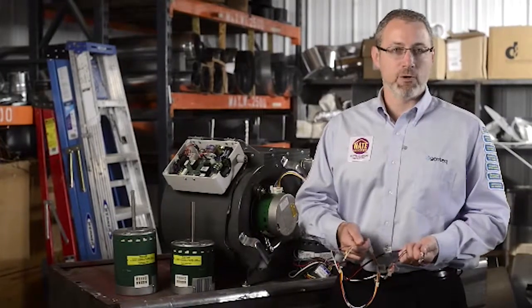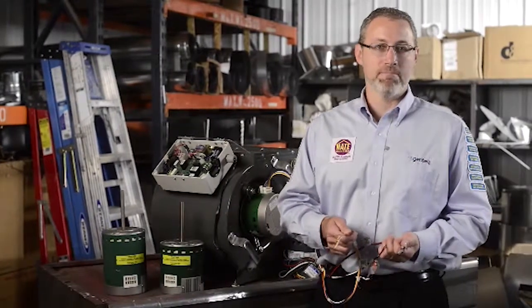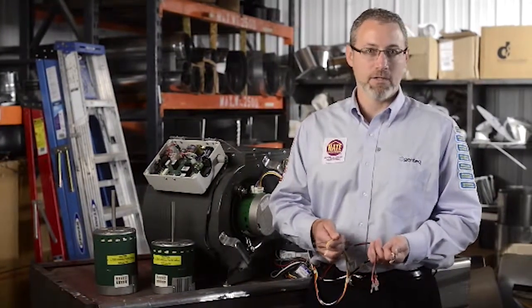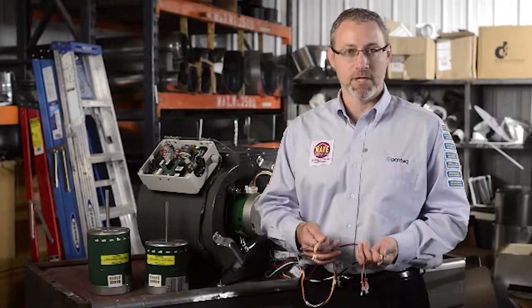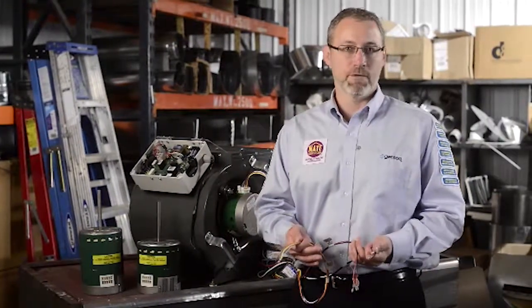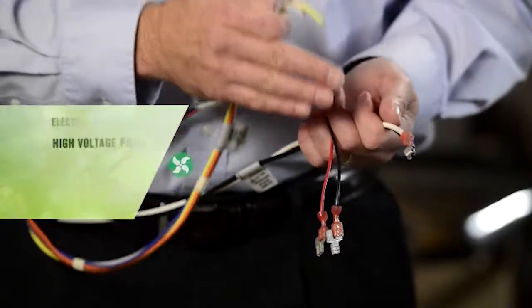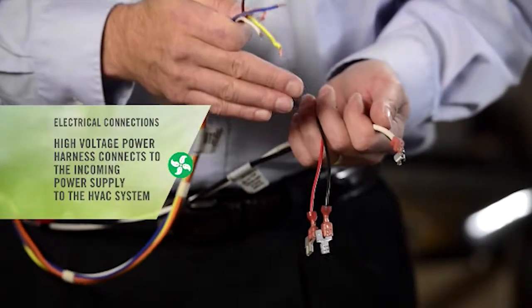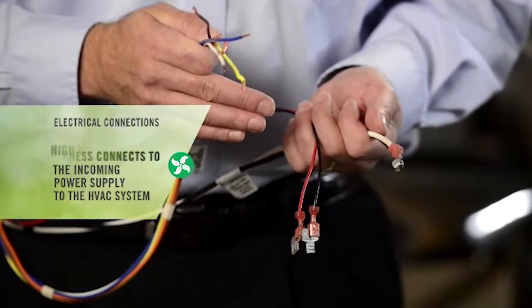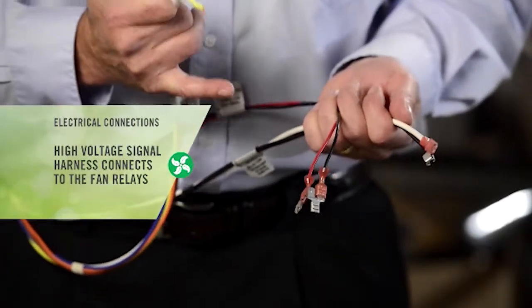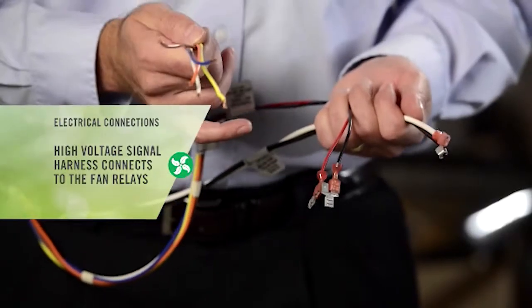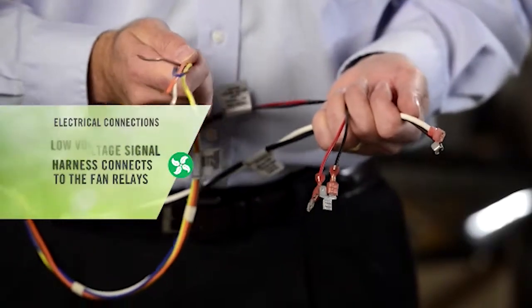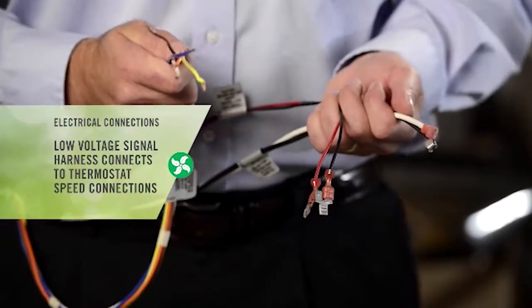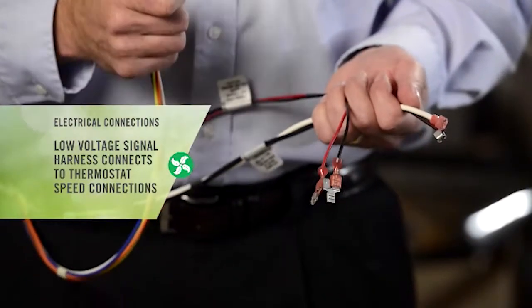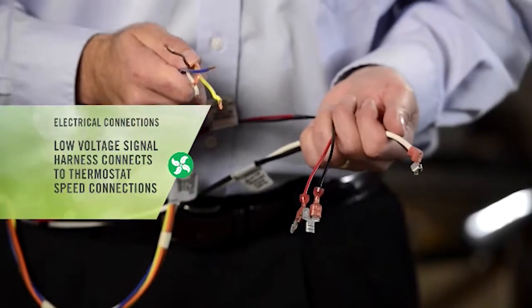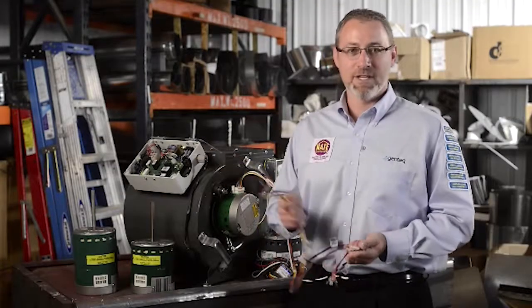At the other end of the Evergreen IM harness, we basically have 3 mini harnesses. Each mini harness is taped and flagged with information telling you what to do with these wires. So let's overview that real quick. The high voltage power harness will connect to the incoming power supply to the HVAC system. The high voltage signal harness will connect to the fan relays that used to turn on the PSC motor speed taps. And the low voltage signal harness will connect to the thermostat connections to select the speeds for each mode of operation. Let's see how that works on the HVAC system.